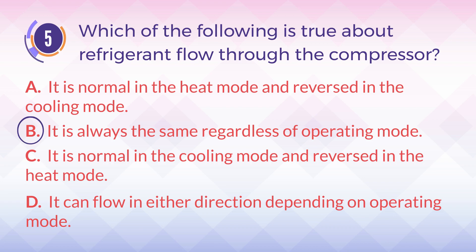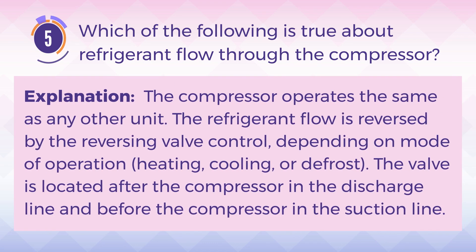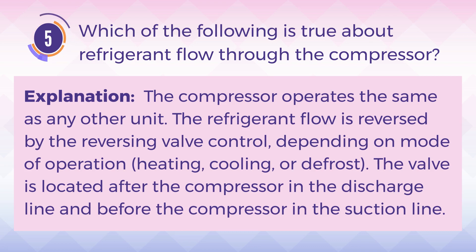The answer is B, it is always the same regardless of operating mode. Explanation: The compressor operates the same as any other unit. The refrigerant flow is reversed by the reversing valve control, depending on mode of operation — heating, cooling, or defrost. The valve is located after the compressor in the discharge line, and before the compressor in the suction line.